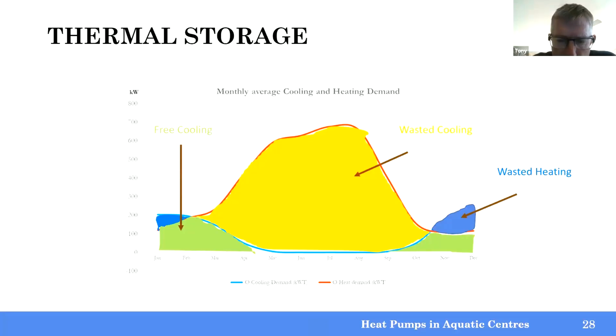If we combine heating and cooling together using a heat pump, we can effectively say we're getting free cooling - any cooling supplied from the heat pump can be considered free. The green shaded areas in this curve show where we can get free cooling in a typical aquatic centre. In summer, when you've got more cooling than heating, you basically need to waste that heat into the atmosphere - that's what the blue sections represent.